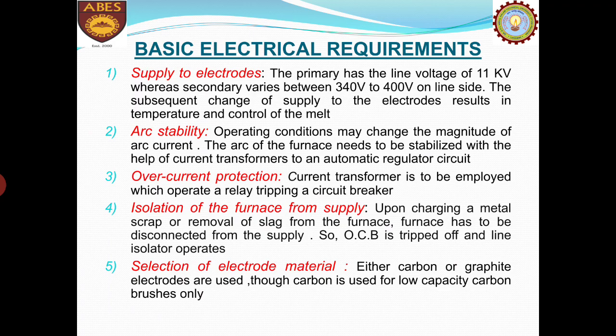Now if I talk about arc stability, how stable your arc is, because we are using that arc only for the heating purpose. So we need the arc produced to be quite stable for the operation, right? With alternate striking of the arc, if we are repeatedly quenching the arc, then igniting again, then quenching again, then controlling again, the electrodes may burn out gradually. It may lead to deterioration of the electrodes. So the electrodes may burn out gradually, thereby increasing the length of the arc, which will extinguish if the gap is not maintained properly.